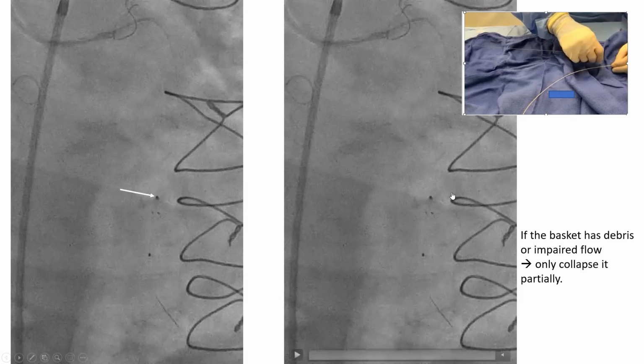So we simultaneously pull the spider wire with this hand while pushing the catheter with the other hand until we collapse the basket. We typically push with this hand more than we pull, but the goal is to keep the basket in place, not to move it and create dissections. So you adjust your push and your pull accordingly. You may need to pull more with this hand grabbing the filter if the filter dives in. So you adjust your push and pull accordingly to keep the filter in place. Usually more push with this hand than pull.